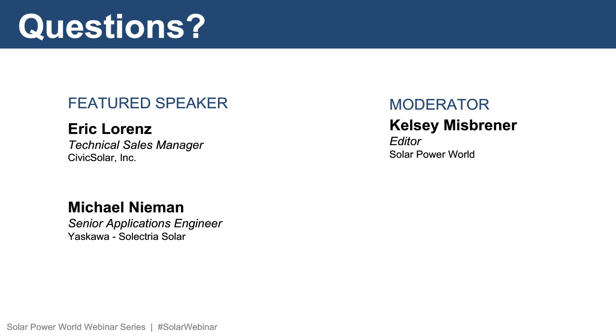The next question is, what do you think is the next logical step for rapid shutdown with NEC 2020? Another great question. What you're going to see from equipment manufacturers is harmonization to allow inverter technologies to communicate directly with module integrated electronics and switches more specifically. There's a lot of work being done in the industry. SunSpec Alliance is one organization working on a communication standard to define what that communication may look like between inverters and module integrated electronics to allow for a uniform command structure to initiate rapid shutdown of PV arrays.